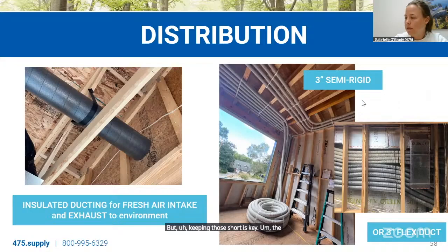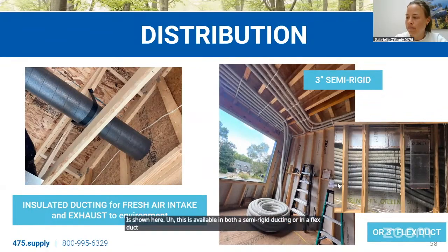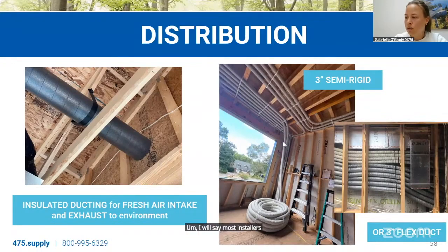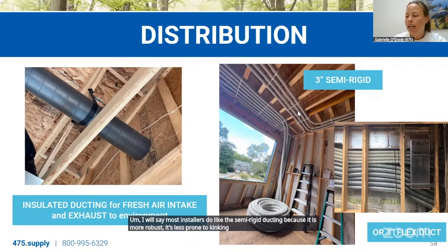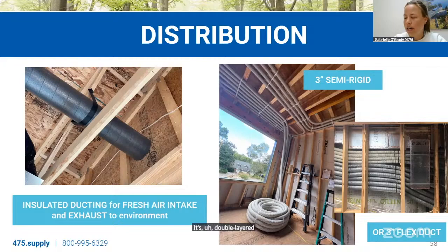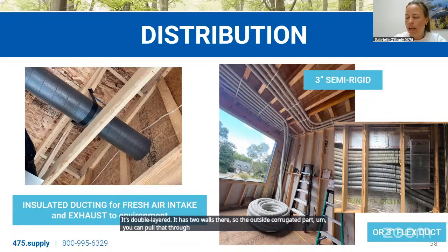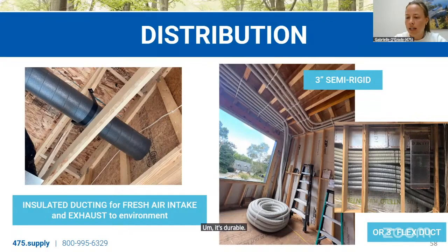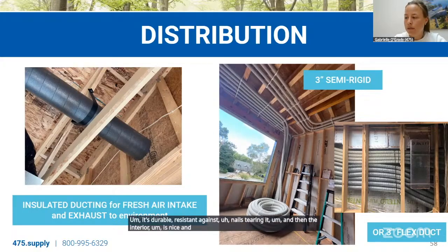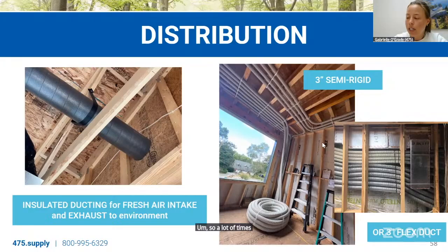The 3-inch ductwork, as mentioned, is shown here. This is available in both a semi-rigid ducting or in a flex duct option. I will say most installers do like the semi-rigid ducting because it is more robust. It's less prone to kinking. It's double layered. It has 2 walls there, so the outside corrugated part, you can pull that through stud bays. It's durable, resistant against nails tearing it, and then the interior is nice and smooth and protected by that corrugated shell. So a lot of times projects do like working with that.